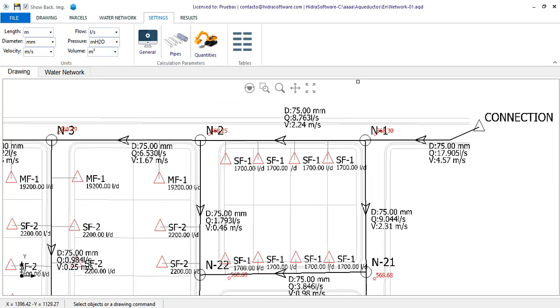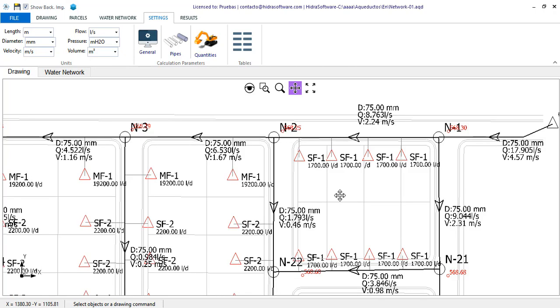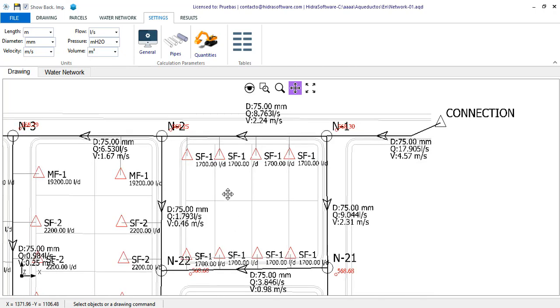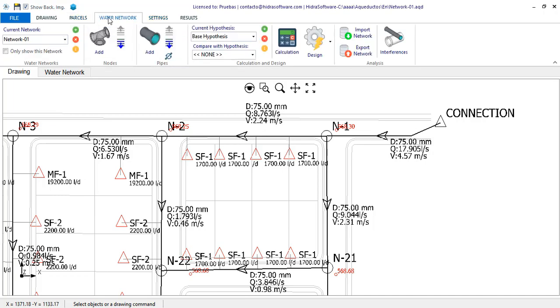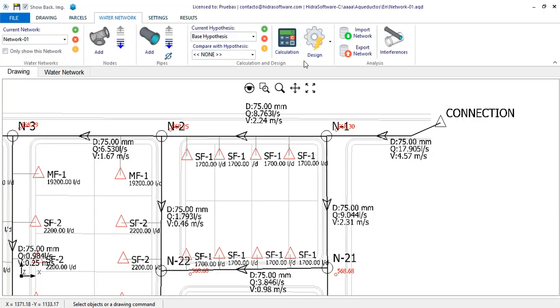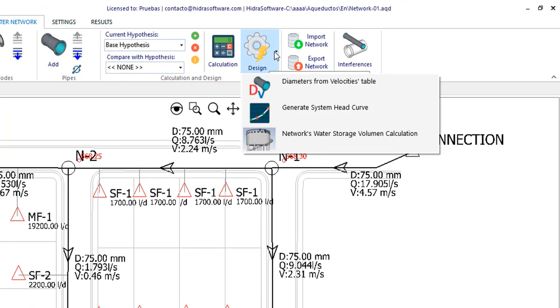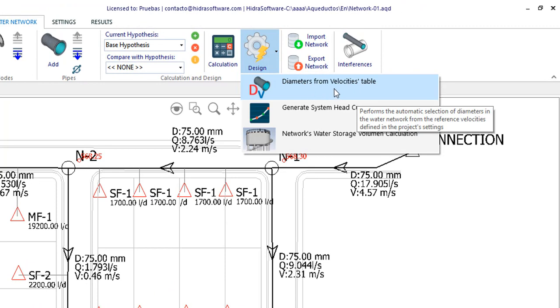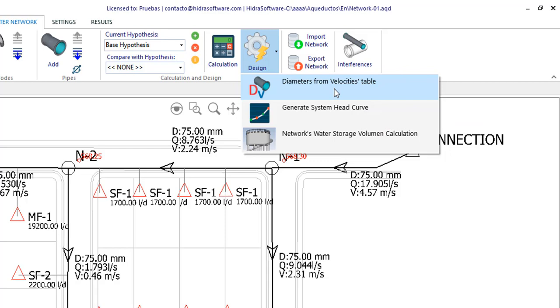If this calculation were done manually, you should know that it is required now to modify, one by one, each pipe section diameter, redoing the calculation so as to make the necessary adjustments to achieve the design velocities. With aqueducts, if you display the available options under the design button, from the calculation and design panel, you will see that there is the option to let the software, based on the velocity design criteria you have selected in the project settings, perform automatically the assignment of diameters to pipe sections.